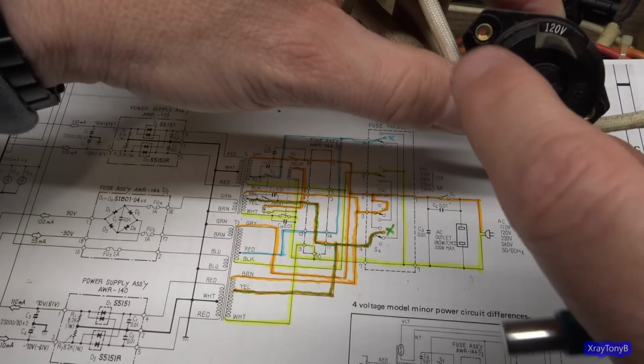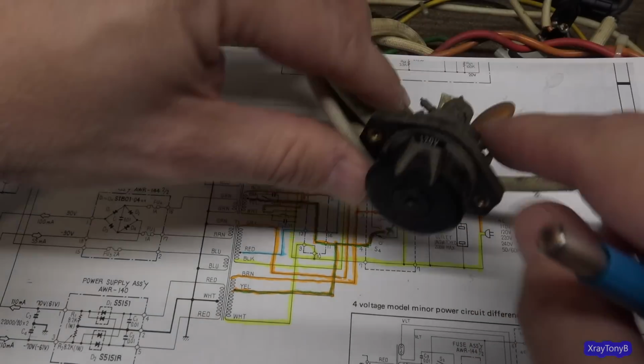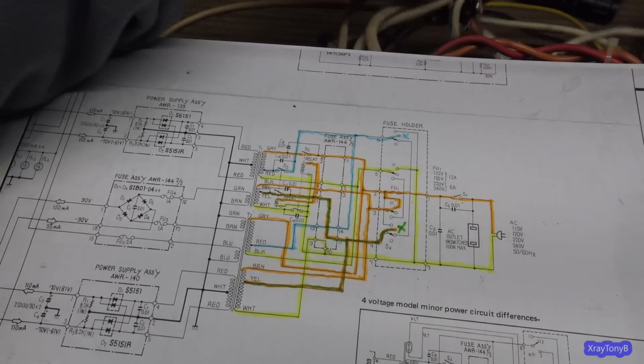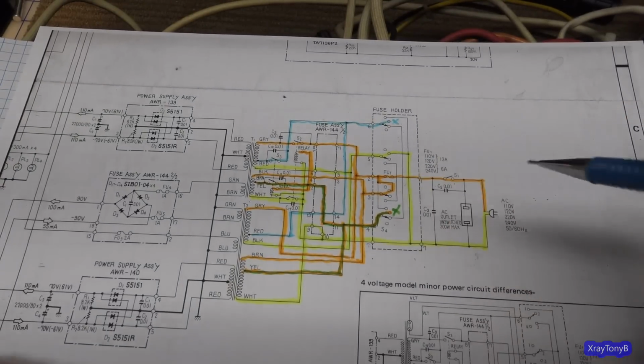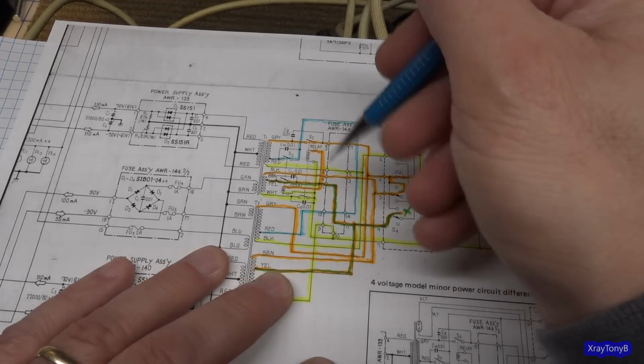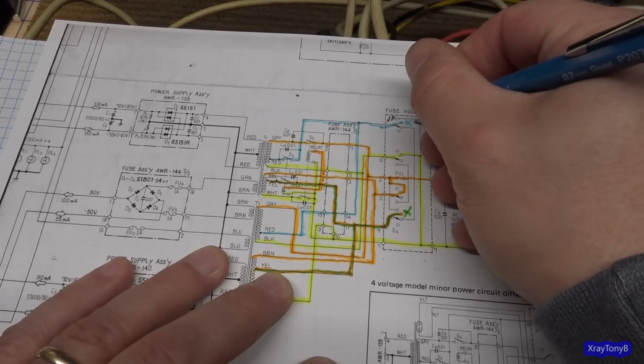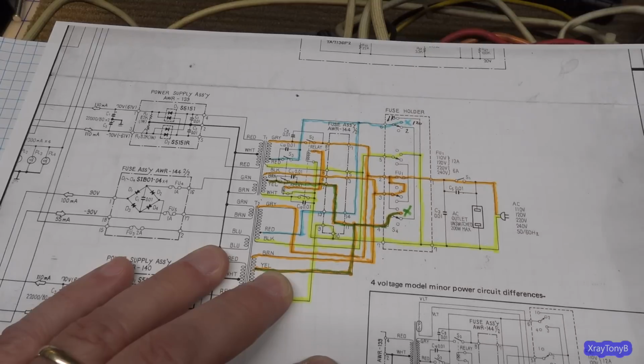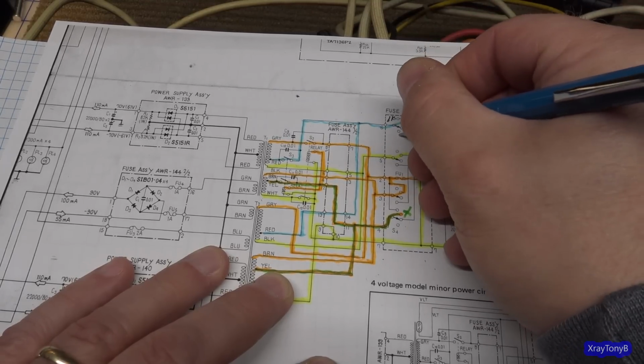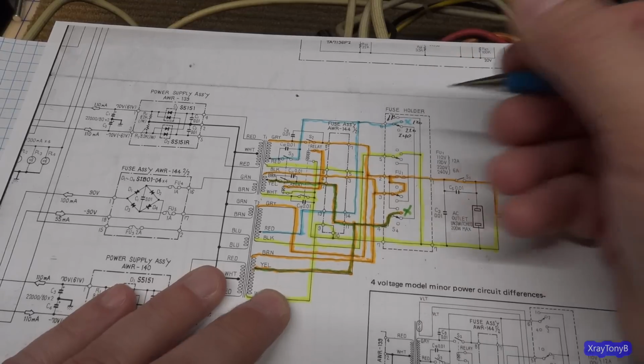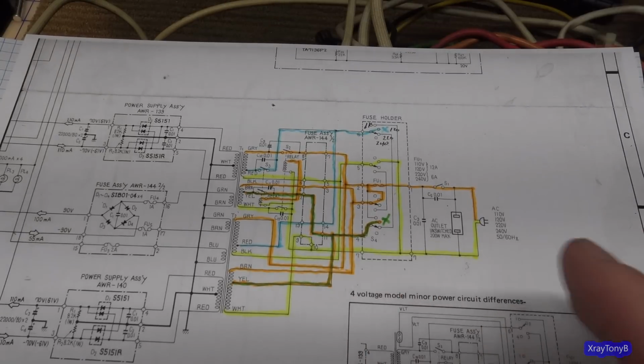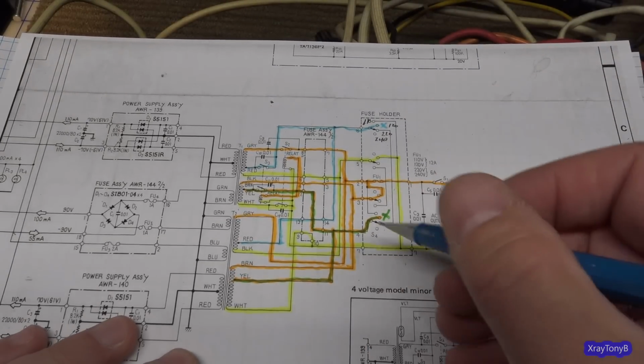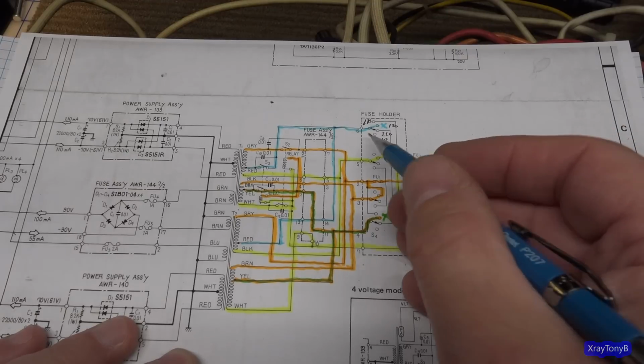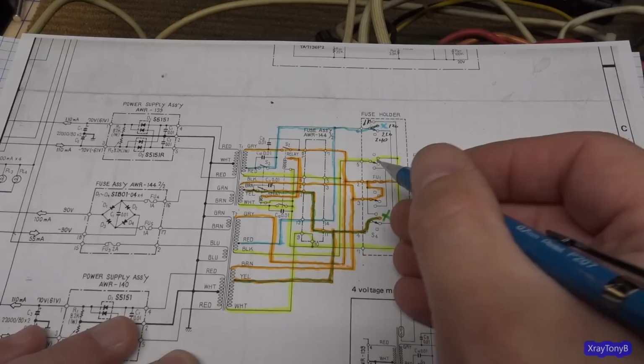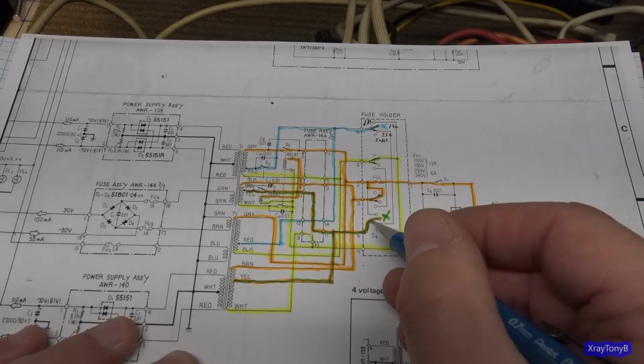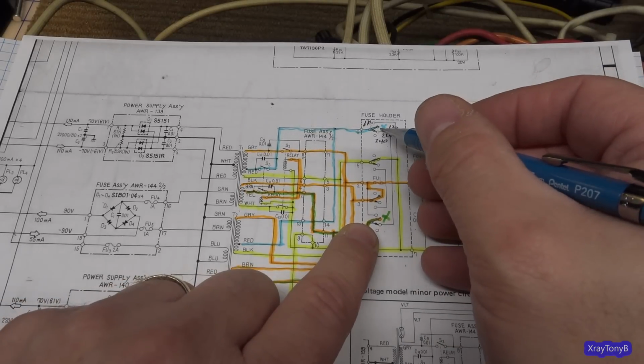By pulling this out and rotating it to whatever voltage, inside here are contacts, just like switches. Depending on how you have them - this top position is 110 volts, this is 120, this is 220 and 240. So depending on what your mains voltage is, that's how you would arrange this. We have 120 volts here in the United States, so this would be connected to here, to here, to here, and to here. Notice these two right here have no connection.